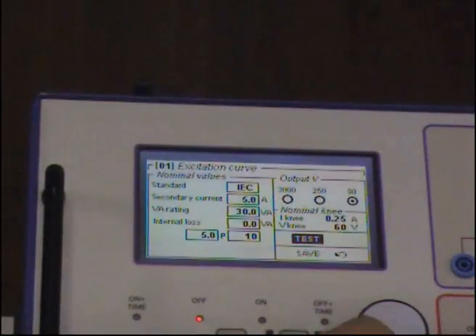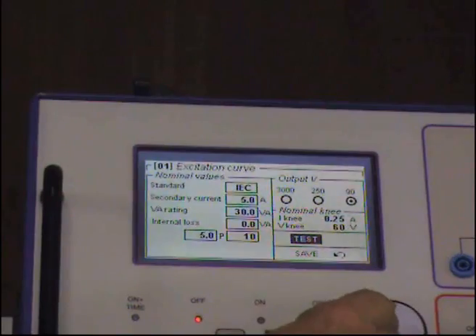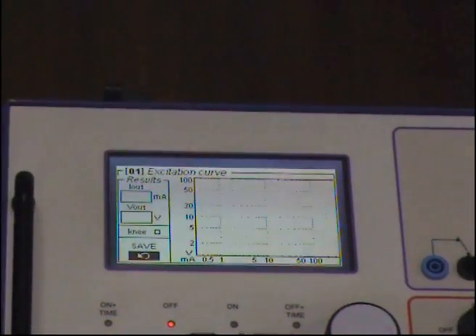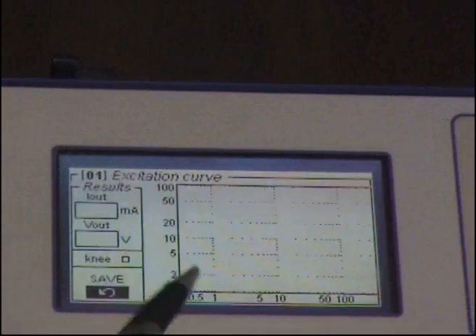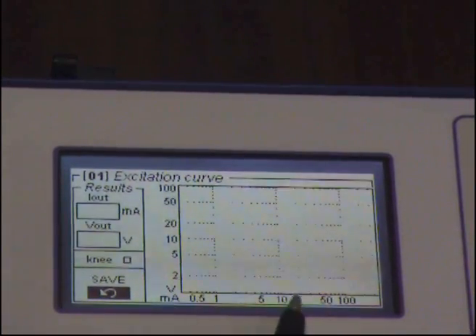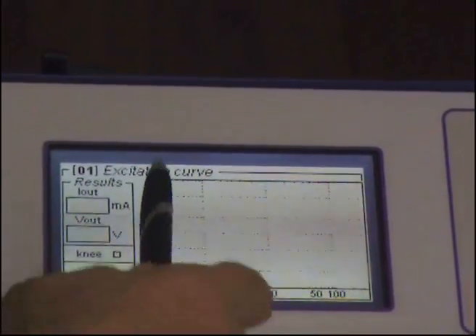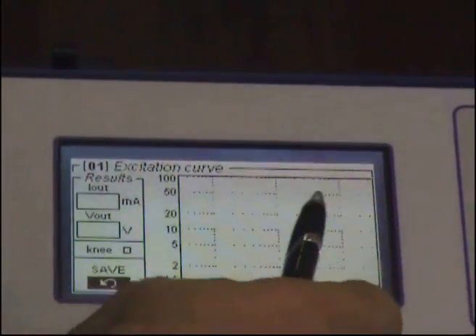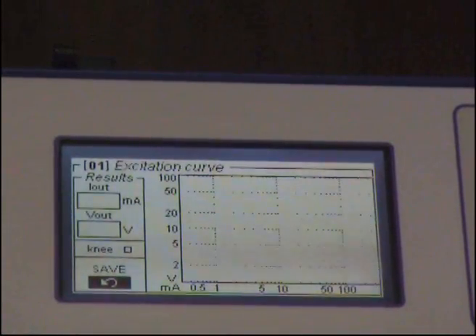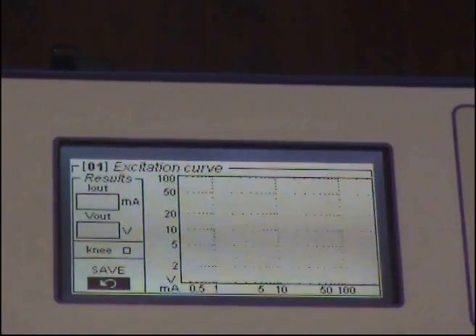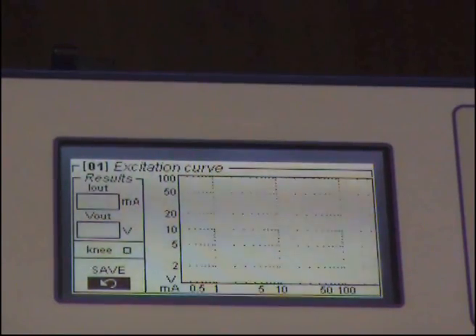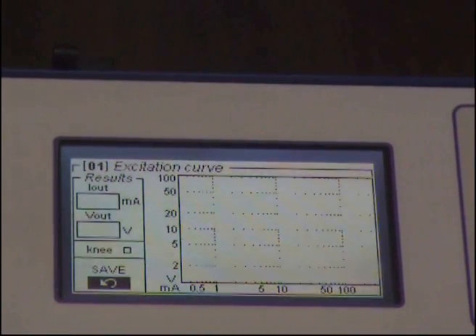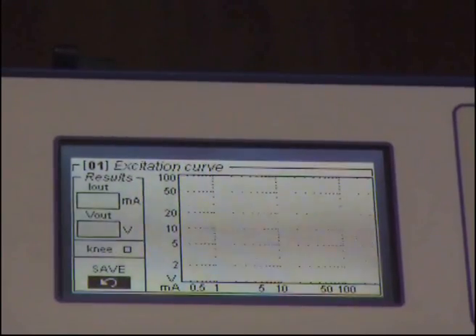So I have connected it and I go to test. As I press test, the next screen shows mA versus volts. On this screen we will see the saturation curve of the current transformer growing as we increase the current.